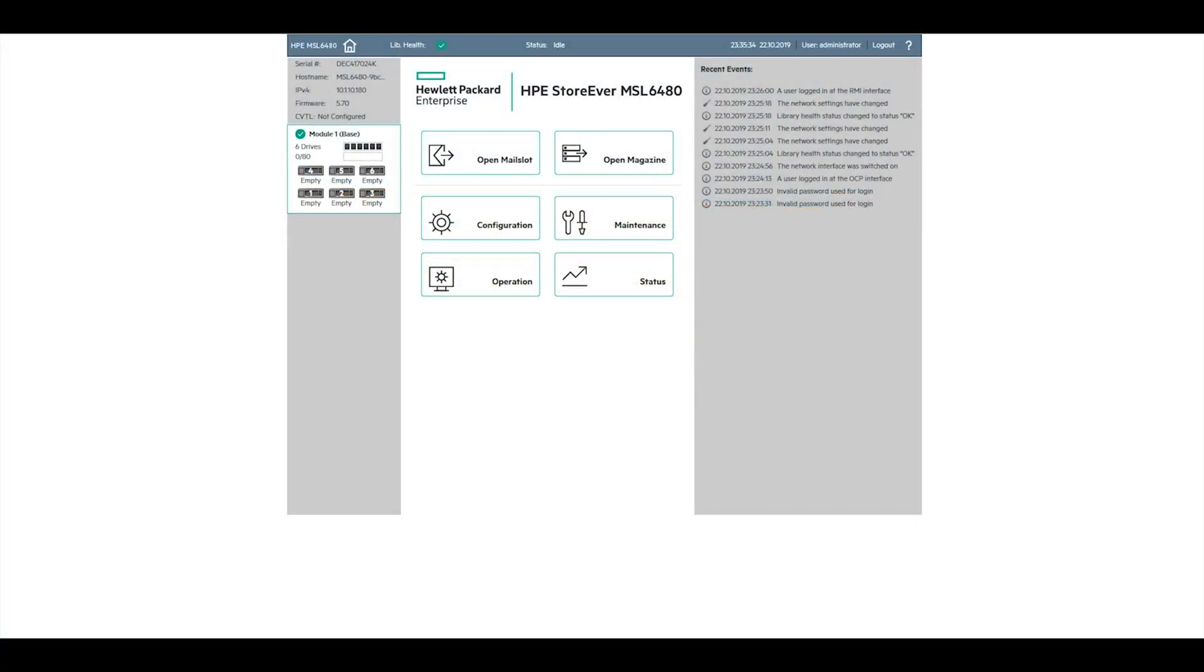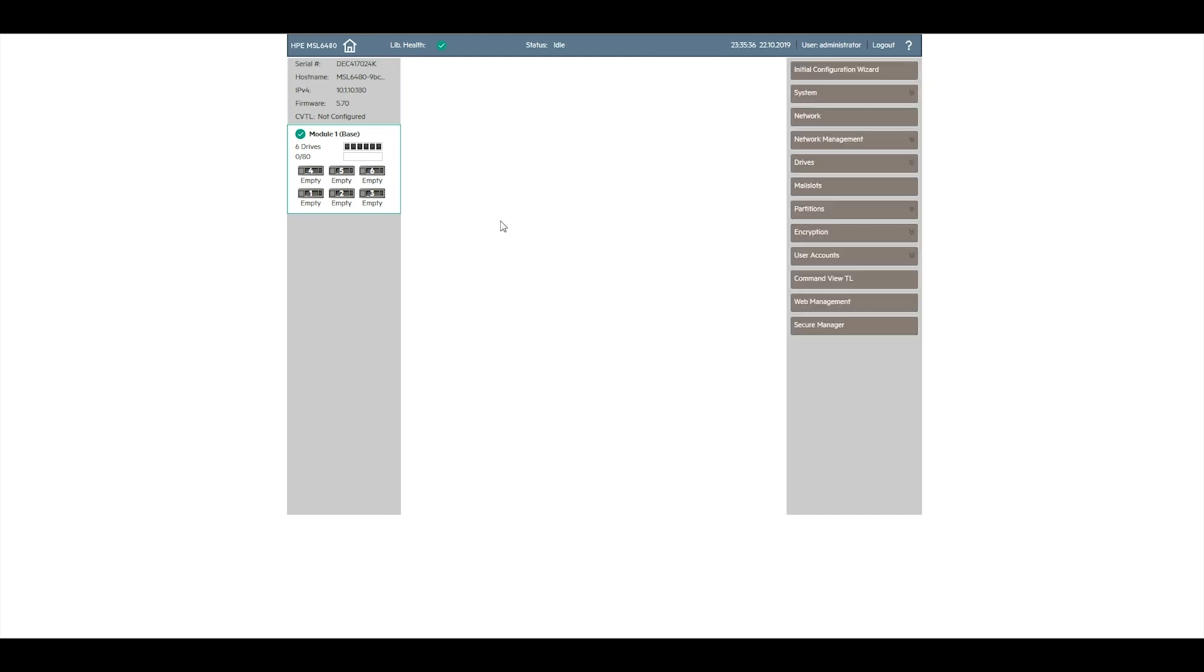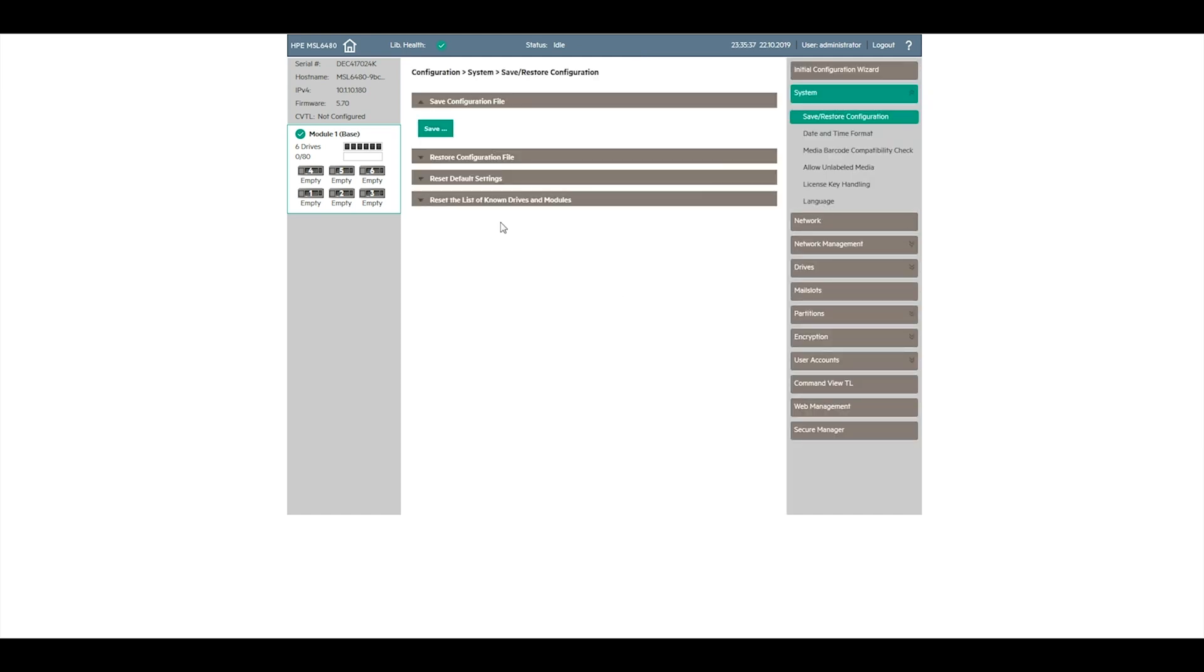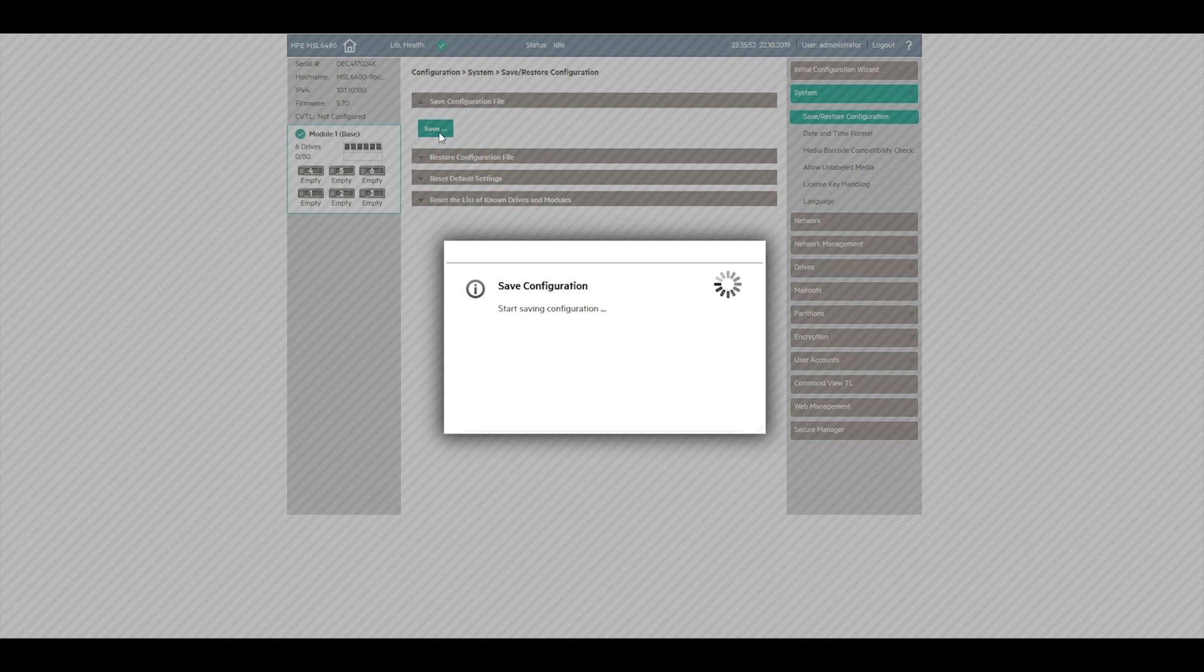Prior to performing this replacement procedure, it is always best practice to log in to the web GUI of the library if possible and save your configuration file. Even though the library configuration is saved on both the base module control card and the library control chassis, it is always a good idea to have a saved configuration file to restore from if needed.